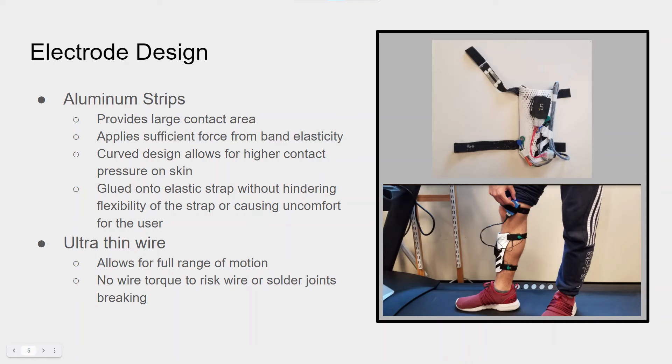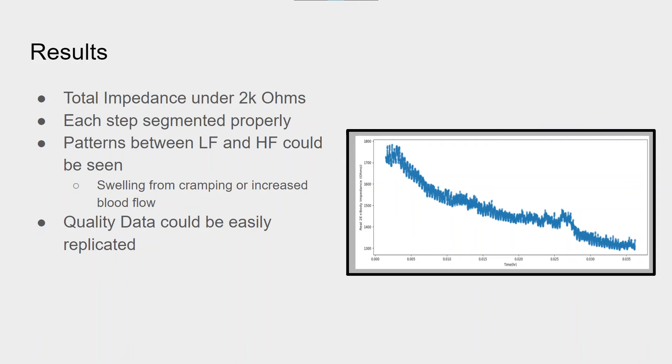They also provide some rigidity with the help of the elastic strap for good pressure onto the skin, which those two are the most important for reducing skin contact electrode impedance: good contact and good pressure. Thin wire is then threaded through the straps of the shin guard to allow for a wider range of motion when using the device.